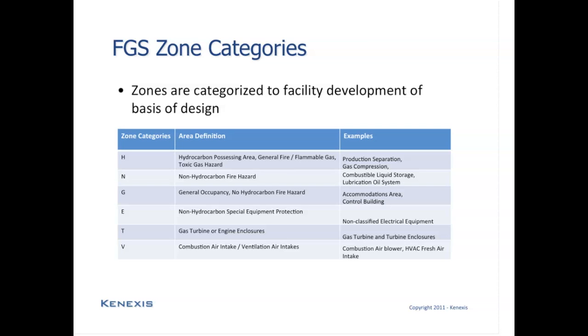The first type of zone is type H, and that is a hydrocarbon processing area. This is an area where the process facility is processing hydrocarbons, and as a result of that processing, there can be leaks, which may result in a fire hazard or a combustible gas hazard. Also, if toxics are being processed in that area, it could result in a toxic gas hazard. And some examples of this type of zone would include a production separation area or a gas compression module.